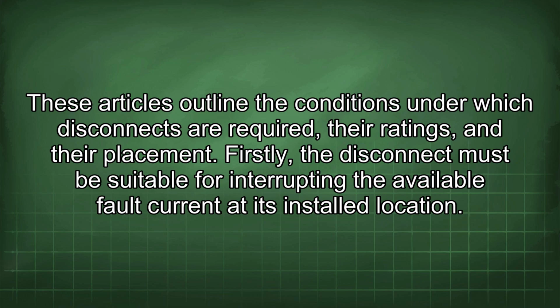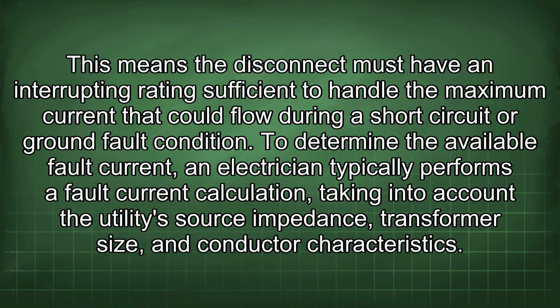Firstly, the disconnect must be suitable for interrupting the available fault current at its installed location. This means the disconnect must have an interrupting rating sufficient to handle the maximum current that could flow during a short circuit or ground fault condition. To determine the available fault current, an electrician typically performs a fault current calculation, taking into account the utility source impedance, transformer size, and conductor characteristics.